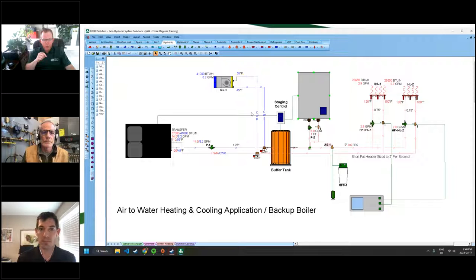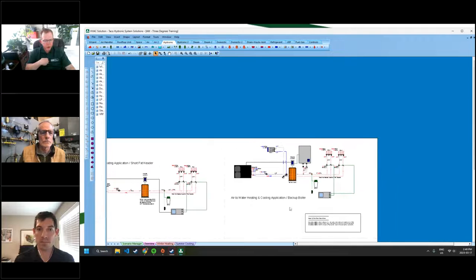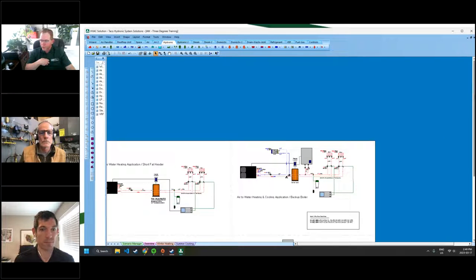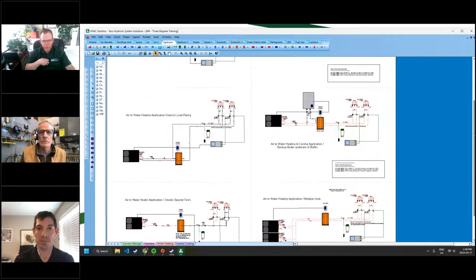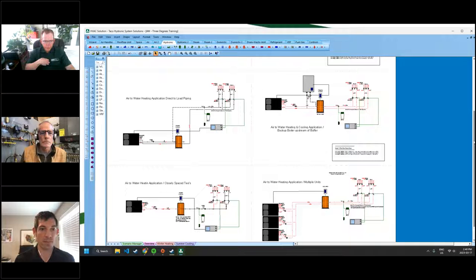is if this boiler is on the left-hand side where the air handler is, where I showed it earlier, we have to be so careful that we don't have boiler water going back out to that heat pump, because that will kill that heat pump. So on this side of the system, I like it. It's well protected, but either is right. Bob can make a great argument for the other way, and so can we. Nothing's right or wrong here. We're just trying to show you a bunch of different options so you can see what comes into play. We're going to move on here.